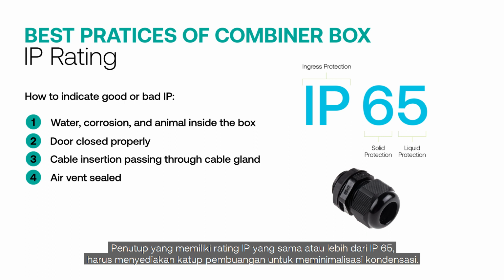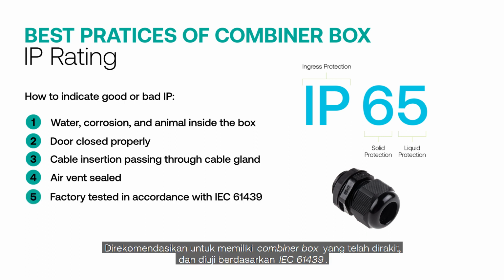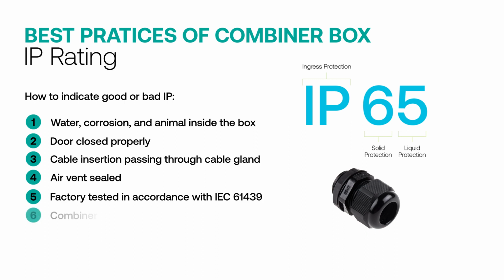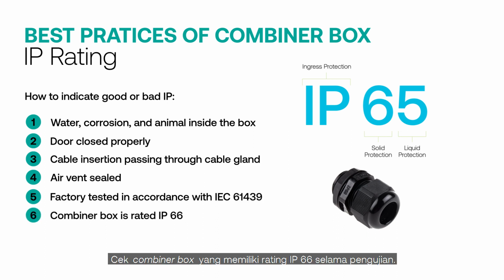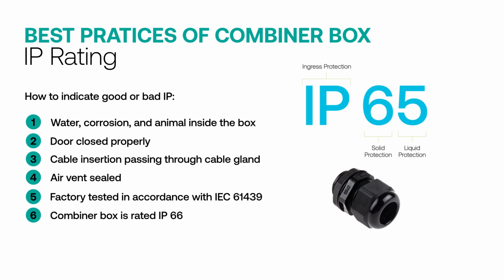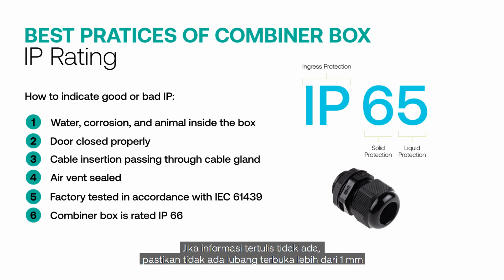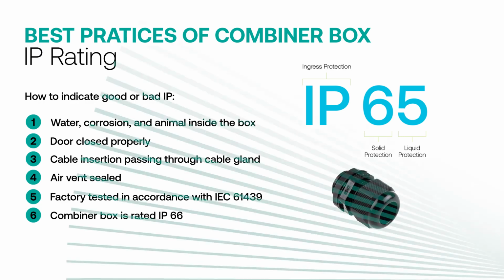Enclosures rated IP65 or greater should provide a drain valve or breather to minimize condensation. It is recommended to have a pre-assembled combiner box that is factory tested in accordance with IEC 61439. Check during commissioning that the combiner box is rated at IP66. If written information is not provided, ensure that there is no open hole bigger than 1 mm.